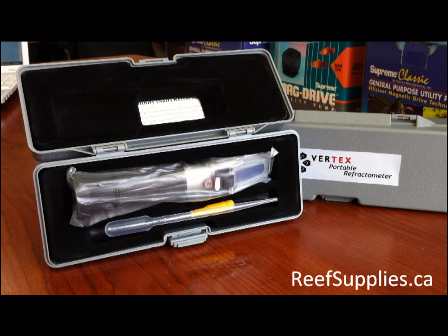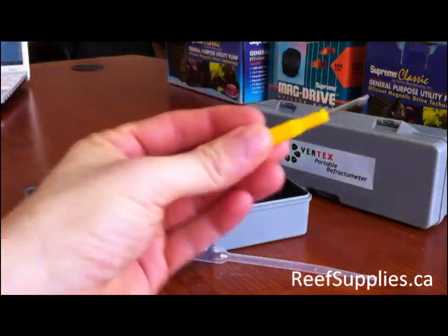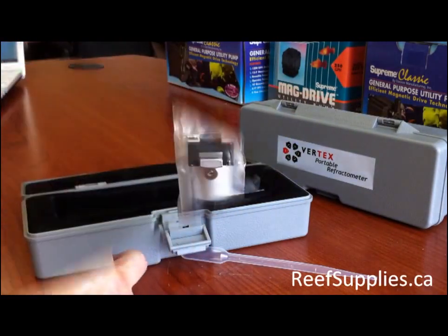This particular unit comes equipped with ATC, which is automatic temperature compensation. Simply put, no matter what temperature your makeup water is, you'll always get the correct reading. It also comes with an adjustment screwdriver for calibration.